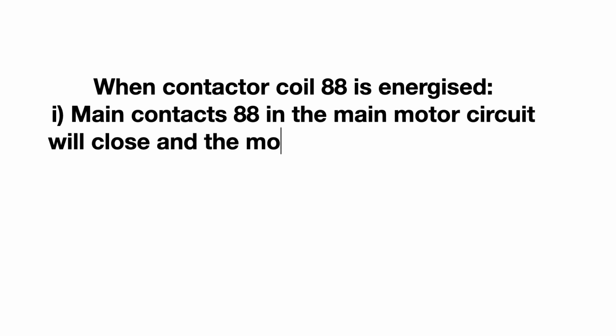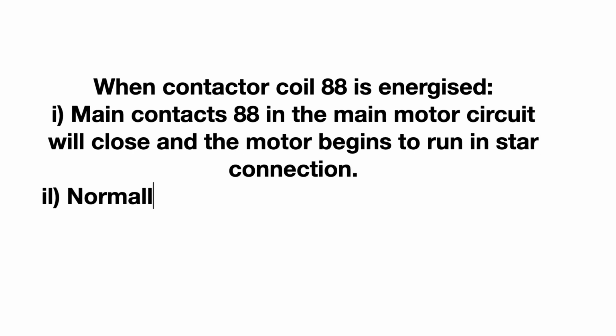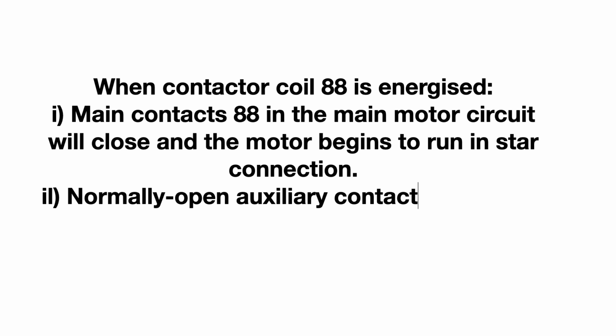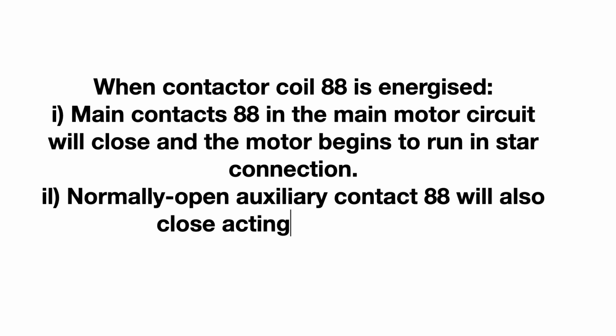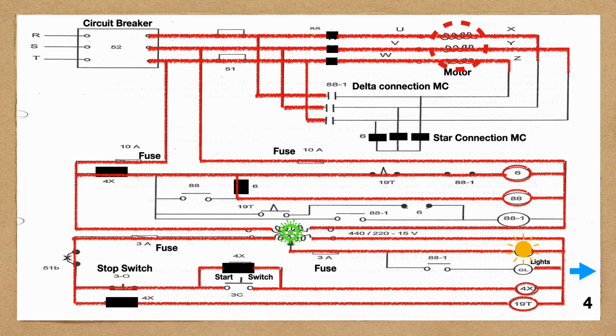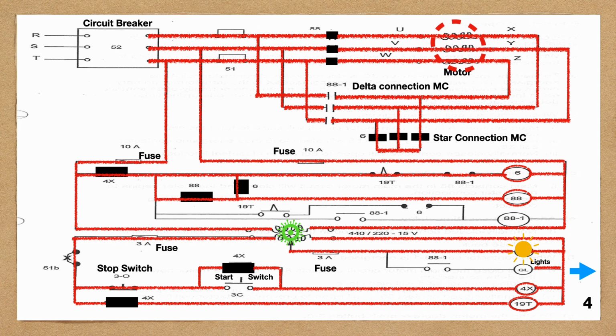When contactor coil 88 is energized, main contacts 88 in the main motor circuit will close and the motor begins to run in star connection. Normally open auxiliary contact 88 will also close, acting as a holding contact. Star connection formed and motor starts rotating.